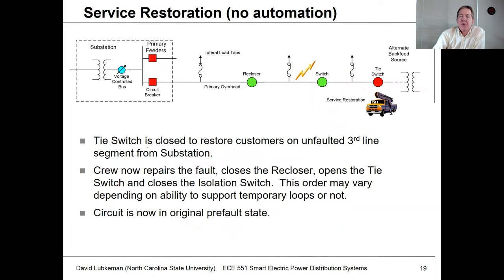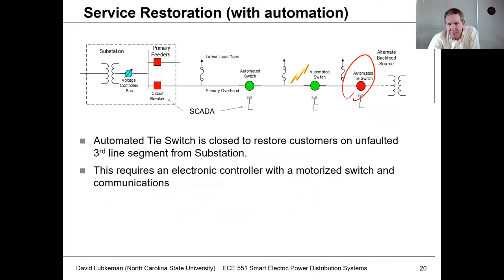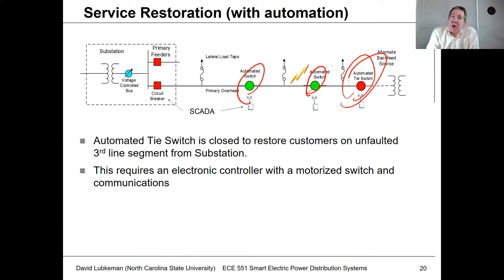For service restoration, one more thing is closing the tie switch to restore customers on the other side. A lot of times this has to be done manually — once the fault is isolated, a crew would drive to the tie switch and close it. But if this is an automated switch, instead of having the crew drive all the way there, a system operator could just close that switch remotely once isolation is complete. You could even have local logic that runs this automatically, with the operator supervising instead of actively doing the switching.